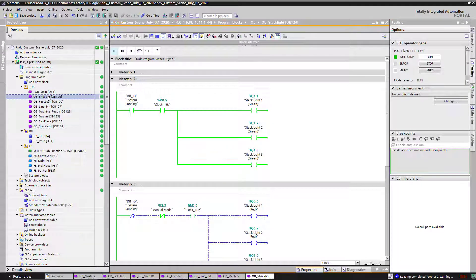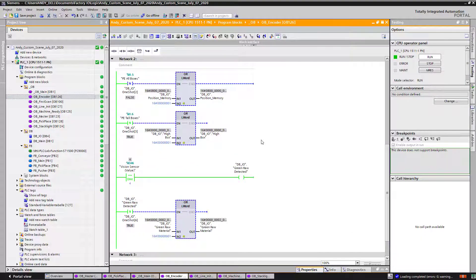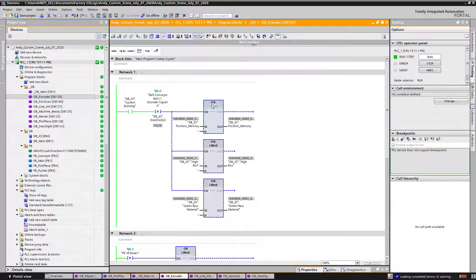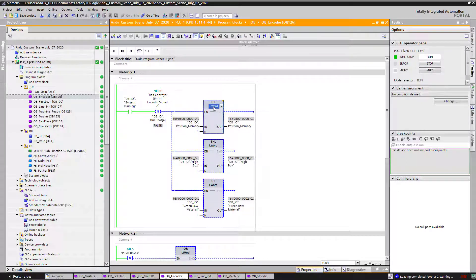Let me take a look at the encoder subroutine. On my encoder subroutine I have three shift registers. Every time I see an encoder pulse, I'm moving and shifting my bits along this long word, which is 64 bits — moving each one of them as the pulses of the encoders are coming in.